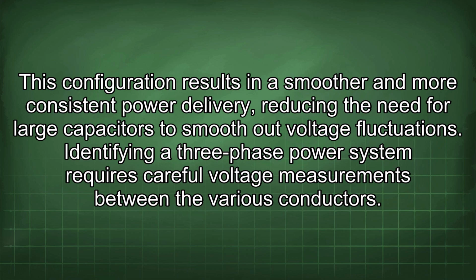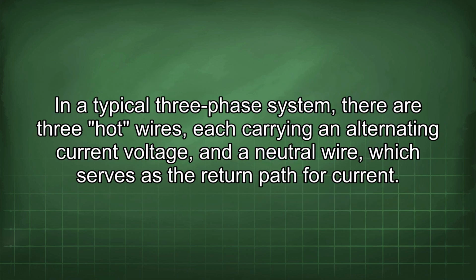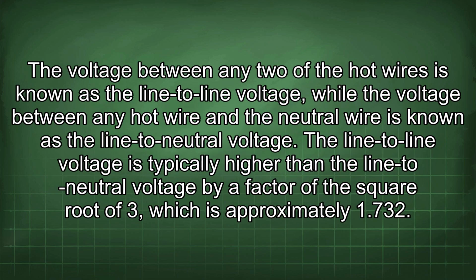Identifying a three-phase power system requires careful voltage measurements between the various conductors. In a typical three-phase system, there are three hot wires, each carrying an alternating current voltage, and a neutral wire, which serves as the return path for current. The voltage between any two of the hot wires is known as the line-to-line voltage, while the voltage between any hot wire and the neutral wire is known as the line-to-neutral voltage.